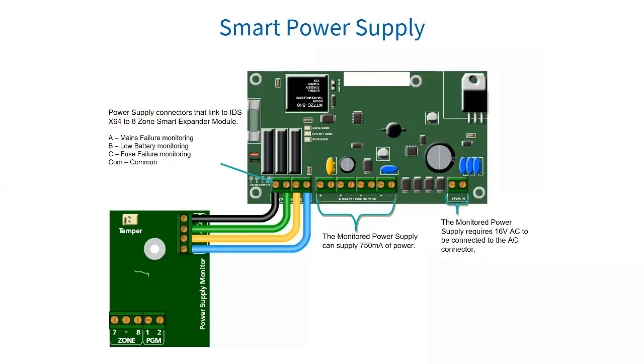We also have the IDS Smart Power Supply module. It allows you to add another power supply with a dedicated 750 milliamp auxiliary power output. It also allows 500 milliamp battery charging without losing the ability to monitor for failures. The IDS Smart Power Supply module has a built-in resettable fuse. To reset the fuse, just turn the module off for a few seconds and then turn it back on again.